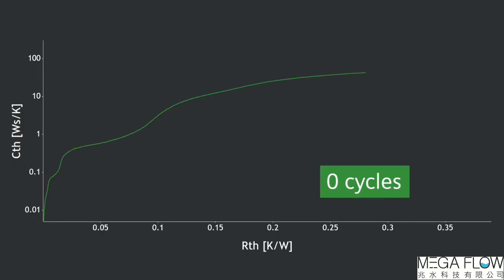Moreover, the thermal transient test results and the generated structure functions can help understanding how the structural defects develop. It can be used to identify root causes of failure and weaknesses of the structure, and hence providing useful feedback to the development.